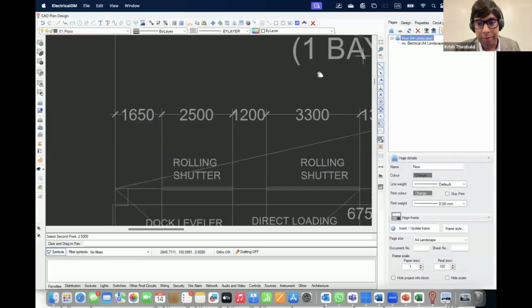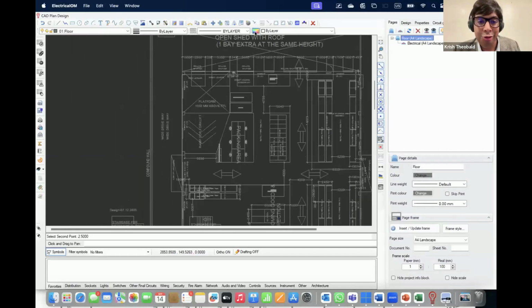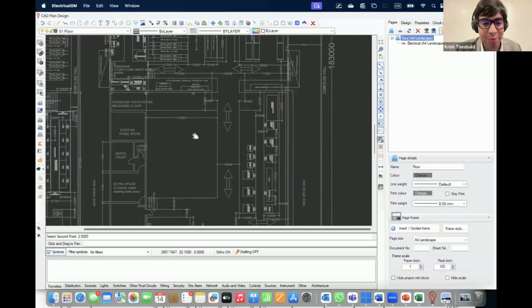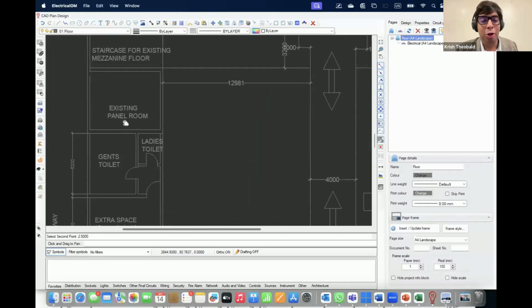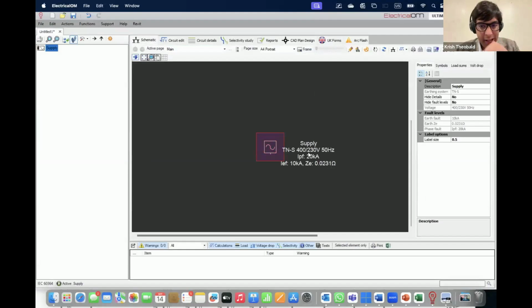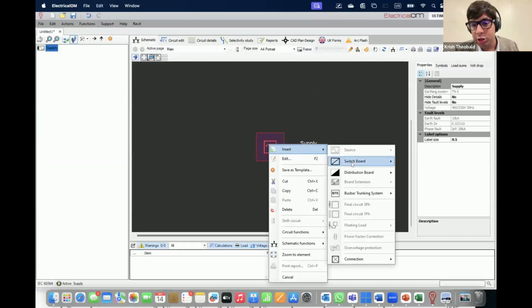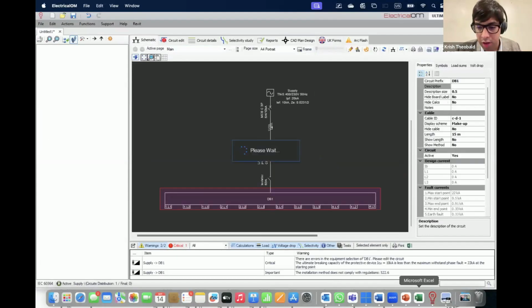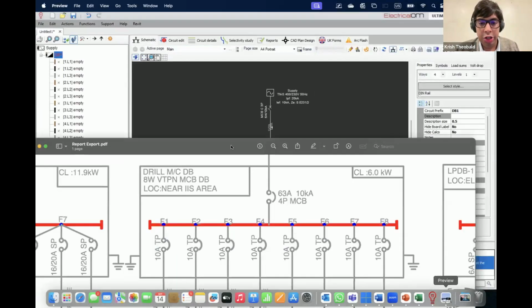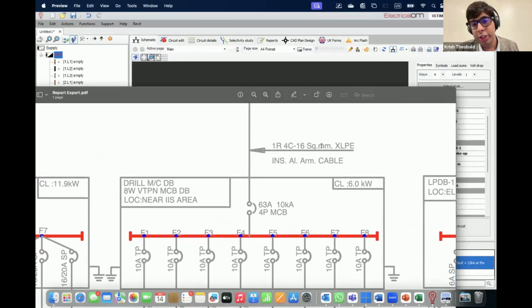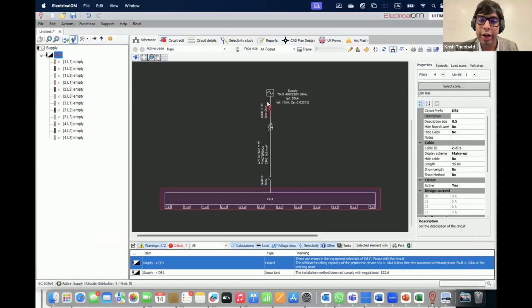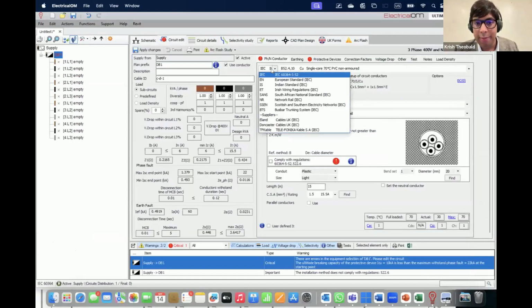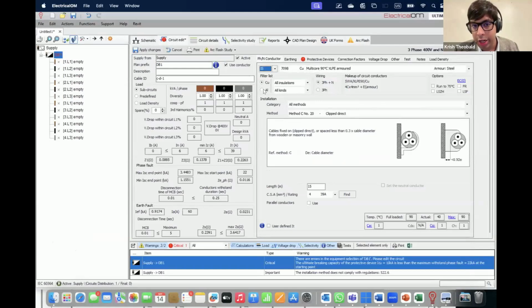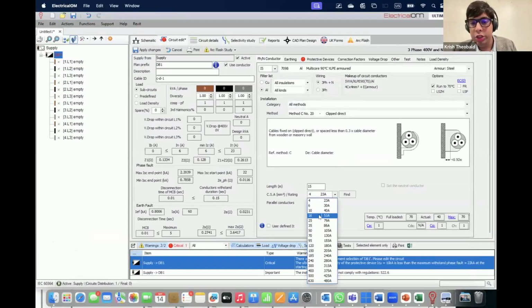So now that we've scaled our drawing, let us be creative because it's not an actual project. So, let us assume that this existing panel room is what we will use. So if we shut this back, right, we've got our supply. It's like this, and let's introduce a distribution board, 3-phase board. Now, if we look at the original schematic, we have a 4-core 16 square mm aluminum armored cable. So let us go ahead and select that. So I am going to select Indian standard, IS 7098 aluminum. We'll run to 70, and we'll clip it direct, and we will do 16 square mm.